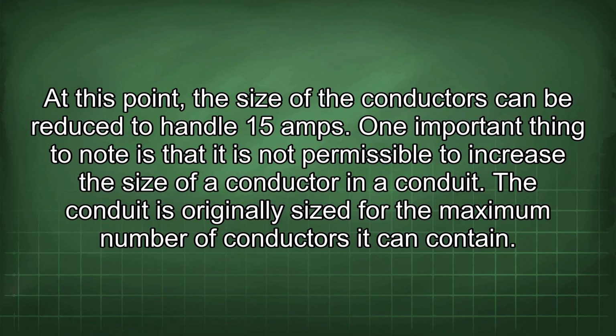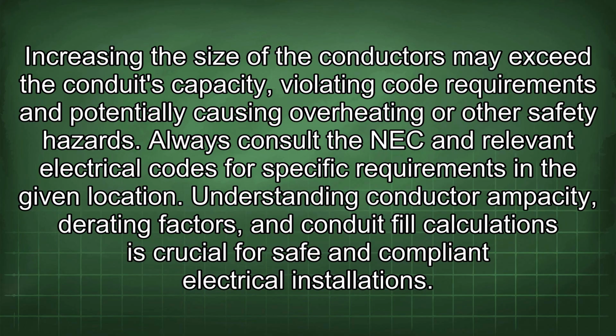One important thing to note is that it is not permissible to increase the size of a conductor in a conduit. The conduit is originally sized for the maximum number of conductors it can contain. Increasing the size of the conductors may exceed the conduit's capacity, violating code requirements and potentially causing overheating or other safety hazards. Always consult the NEC and relevant electrical codes for specific requirements in the given location. Understanding conductor ampacity, derating factors, and conduit fill calculations is crucial for safe and compliant electrical installations.